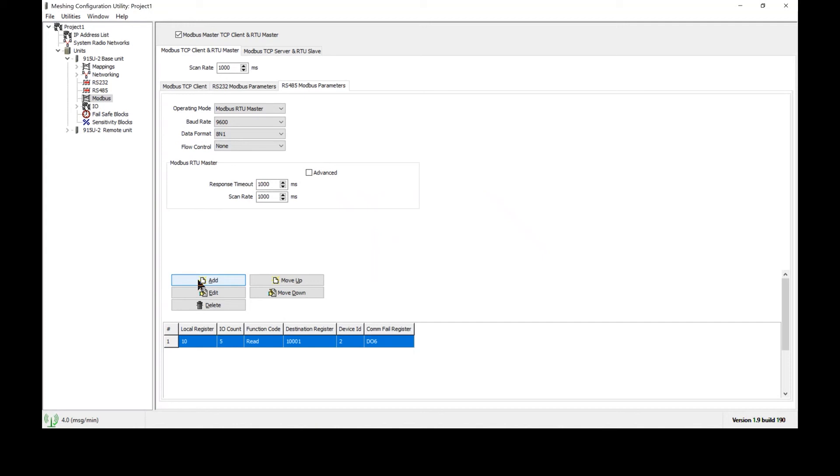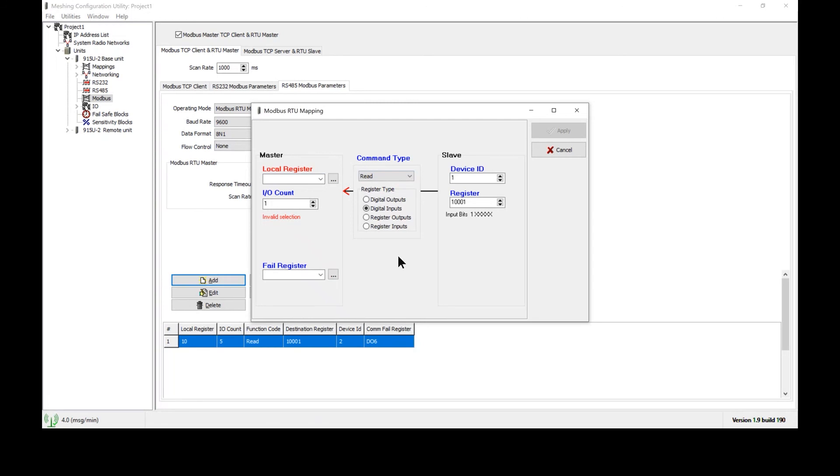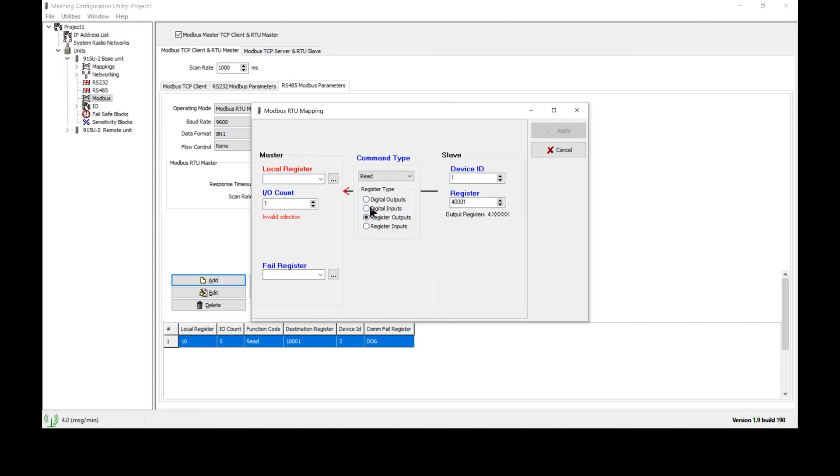Next we need to create Modbus RS485 mappings and these will be a very similar orientation to the Modbus TCP mappings we just created. The first step is to determine the flow of data. In this case we'll select a read input. If we have digital signals that we wish to send we select digital. If we have analog signals that we wish to send we select analog. As you can see when I select register inputs it allows me to choose from the 30,000 series of analog values. If I select register outputs I can now transfer values from the holding registers and similarly with digital inputs. The prefix is determined by selecting digital in, digital out, registers in or registers out and that allows us access to the full range of Modbus registers.